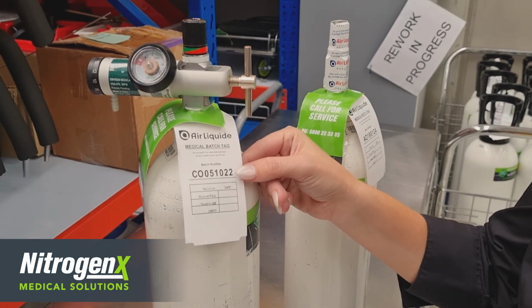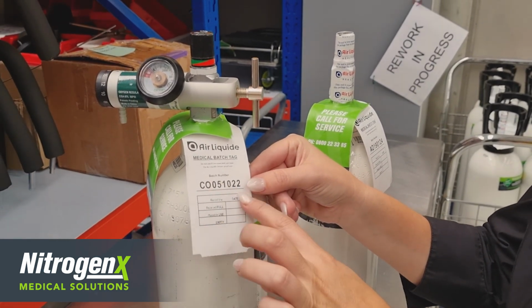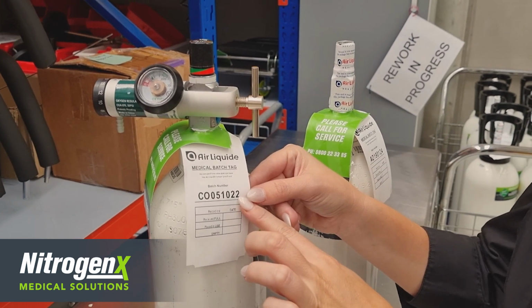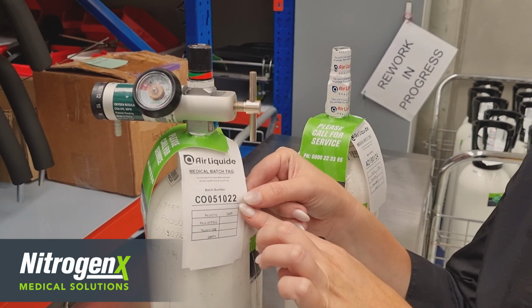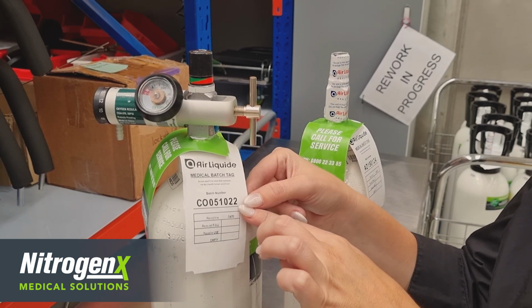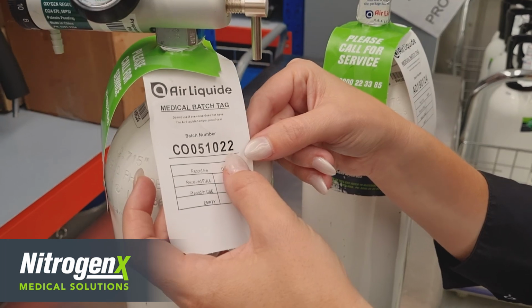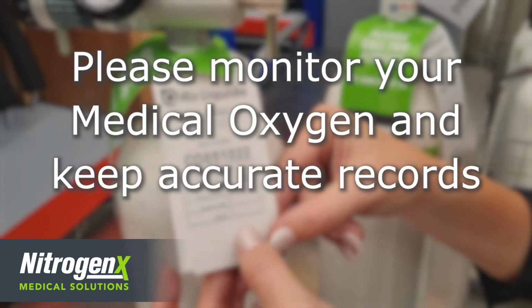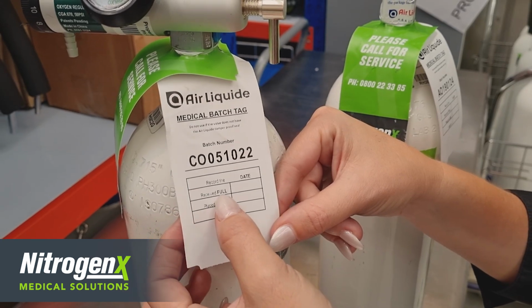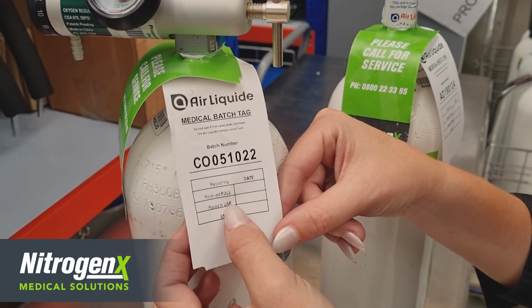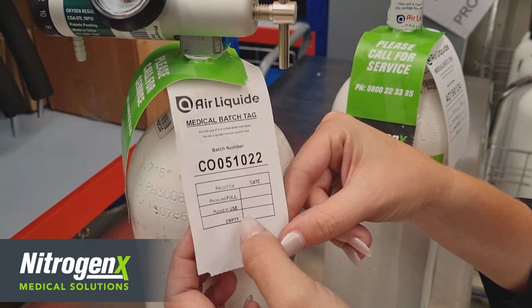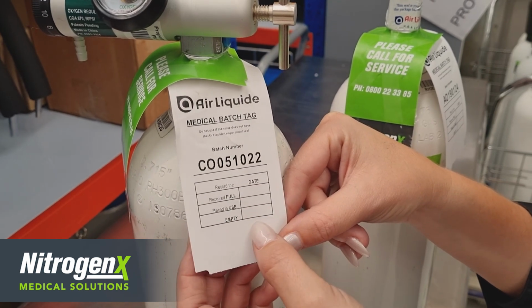Each cylinder will come with a medical batch tag and a batch number on that tag. This batch number is also a date, and the date reflects the last time the cylinder was filled. So in this case, we're looking at the 5th of the 10th, 2022. There are also three fields which need to be filled in. They are when the cylinder was received in full, when it was placed in use, and when it was empty. These need to be filled in by the customer.